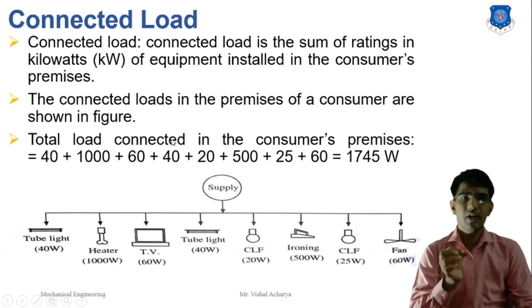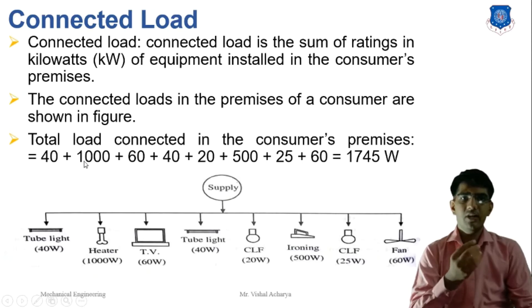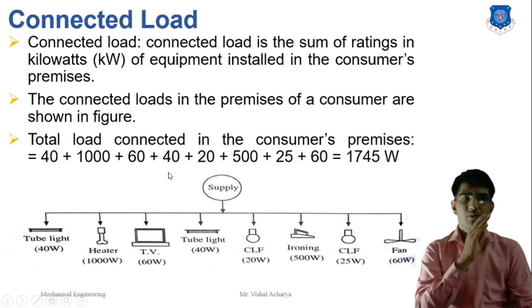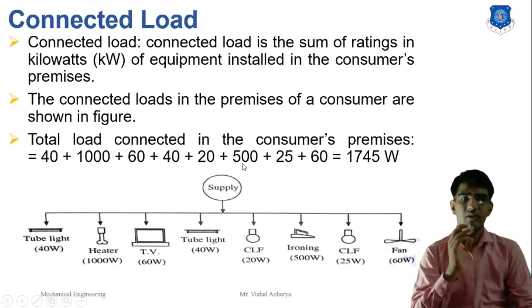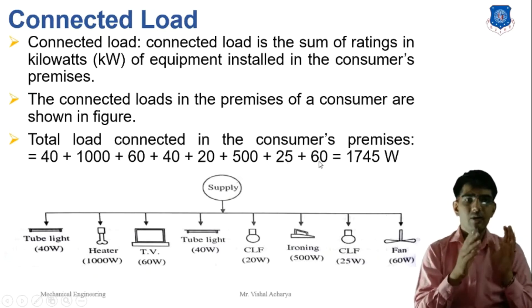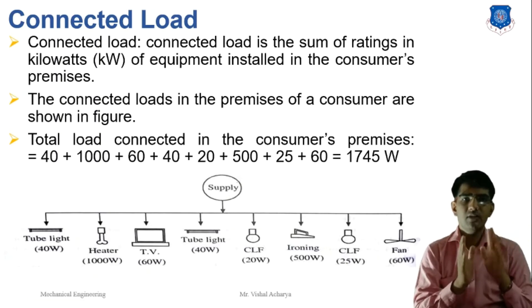The total connected load is: tube light 40 + heater 1000 + TV 60 + tube light 40 + CFL bulb 20 watt + iron 500 watt + CFL 25 watt + fan 60 watt. The total connected load for this system is 1745 watt.